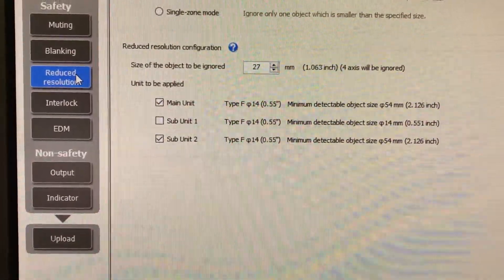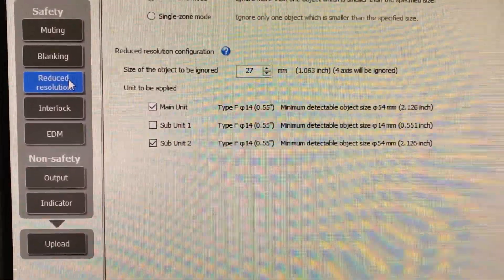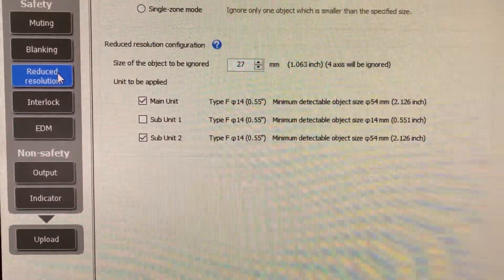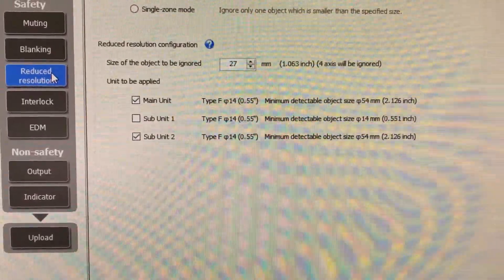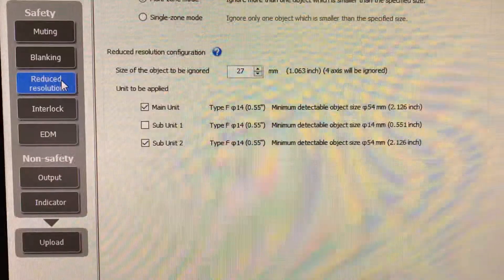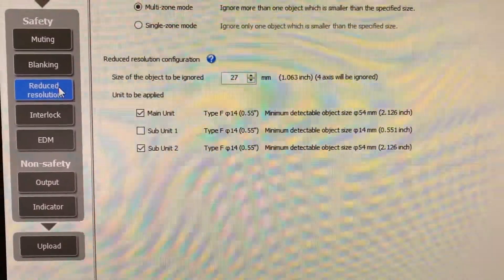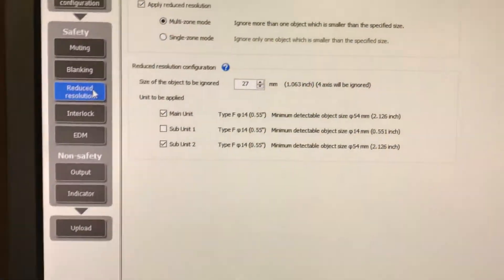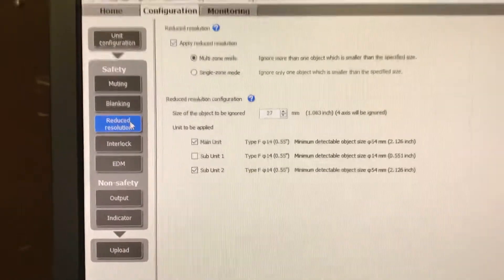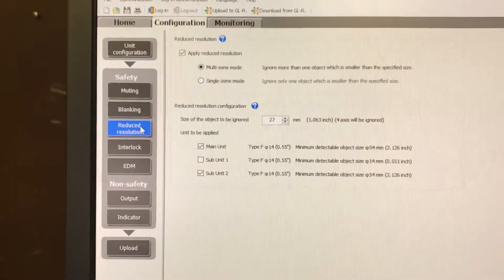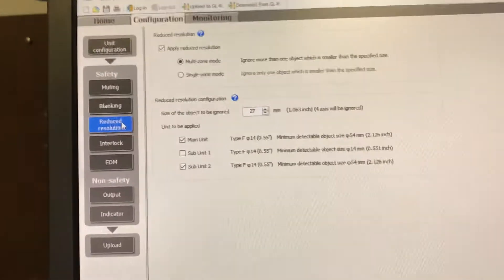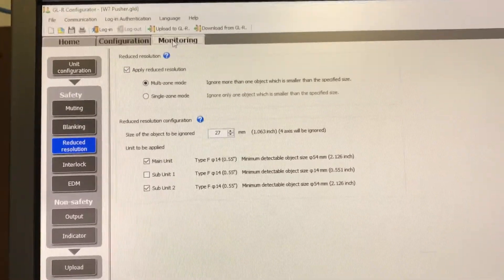So it would take several of the LEDs and physically show them as 27mm or roughly one inch. That would, if something larger than that, say a hose and a finger go in, then your safety relay. And again, you can monitor.